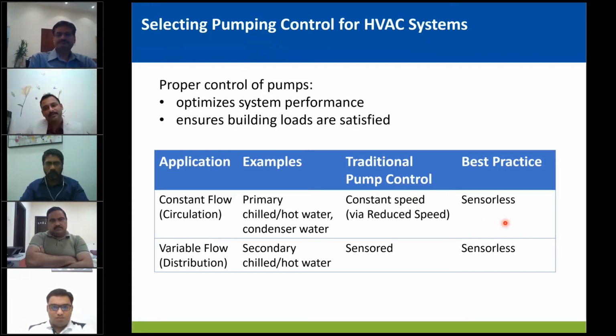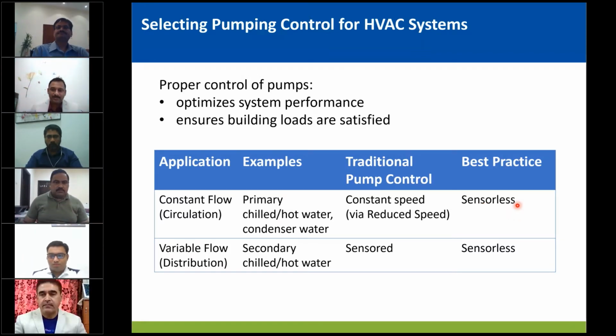But in best practices, when you know flow directly and you program the flow, the smart pumps can maintain the right flow required to the equipment, and thereby not just save energy on pumps, but also save energy on larger pieces of equipment like chillers, because it maintains the required flow rate, and thereby the chiller is more efficient in operation all the time. Now that's for constant flow applications.